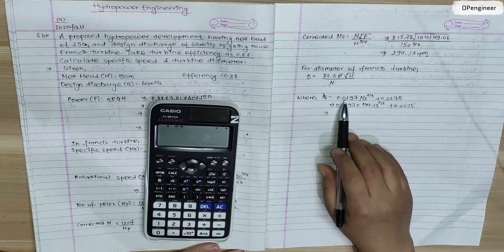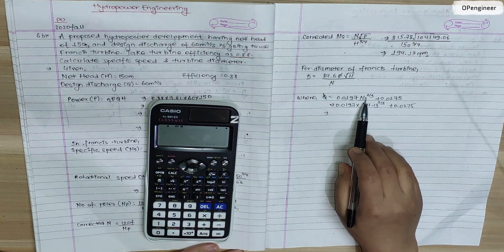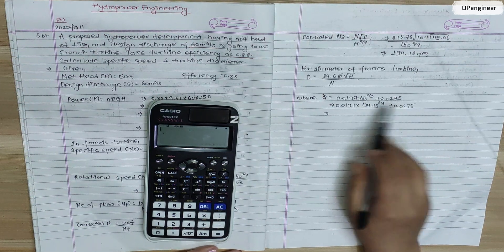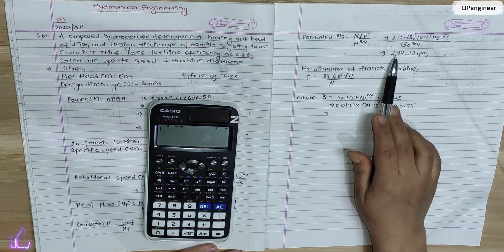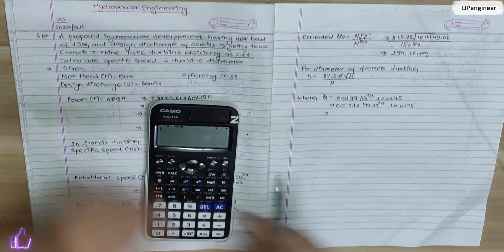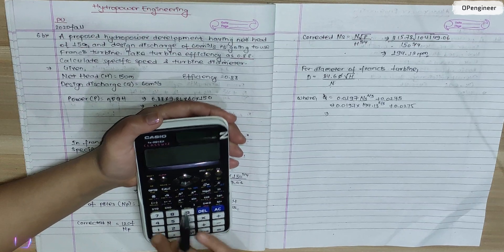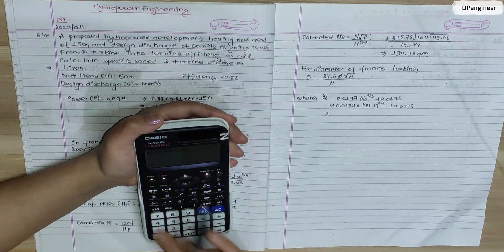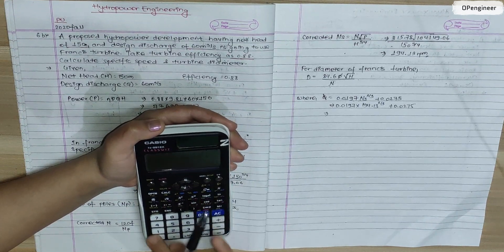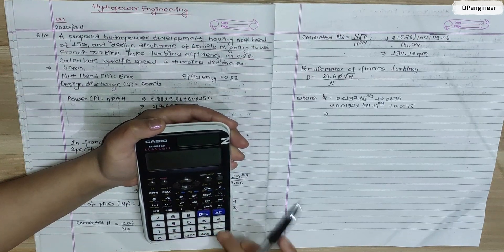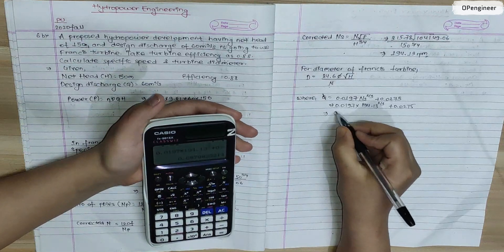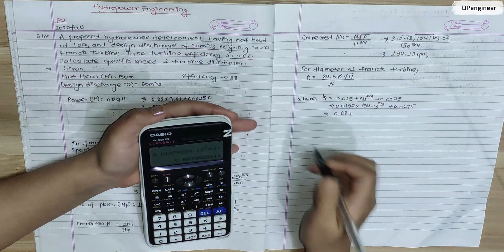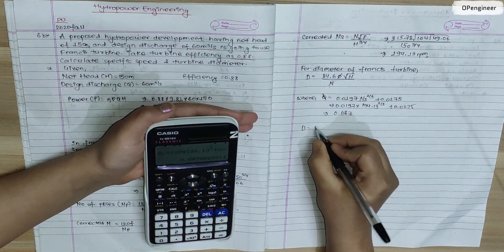The corrected specific speed is 194.13. Then we calculate 0.0197 into 194.13 to the power 2 by 3 plus 0.0275. We calculate phi value 0.687. With phi value we can calculate the diameter.